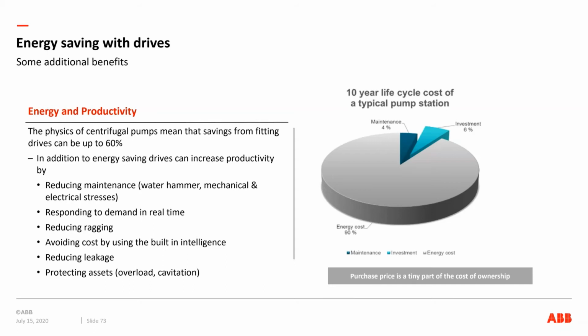But some of the other advantages: less mechanical wear and tear. When you start a pump, let's just say it's a 2,000 gallon per minute pump, when you turn it on, it goes 2,000 gallons per minute. That means 2,000 gallons per minute goes all the way through every pipe, every elbow, every distribution section of the piping, hitting it instantly as it moves down the line. And that can cause main breaks. We've seen main breaks, cities and counties gushing all over the place. It causes mechanical breaks inside of buildings where the elbows come loose. It also causes the pumps and motors to jerk on the ground and break the footings that they're mounted on, whether the basin or the concrete. So there's some mechanical wear and tear.